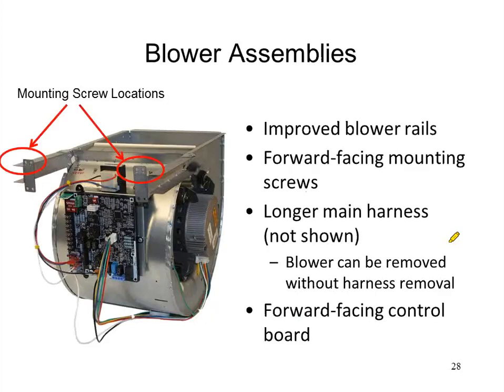This is a little picture of the blower assembly I was talking about. Like I said, you can take out the screws on this guy and slide this whole blower assembly out. You can actually slide it all the way out of the furnace, and they do give you enough wiring whip down here to take this guy out and set him on the ground and then service the variable speed ECM motor from there. Obviously, you should do that with the power disconnected. But you can pull them all the way out and not have to disconnect any of the wiring in order to get to that motor bell.